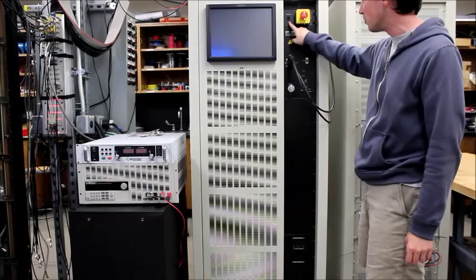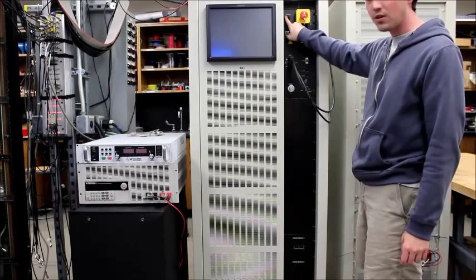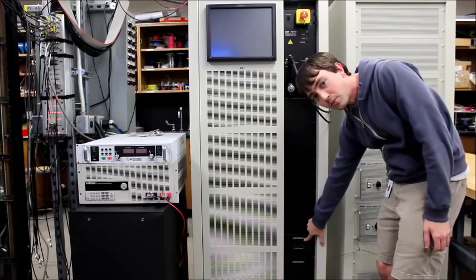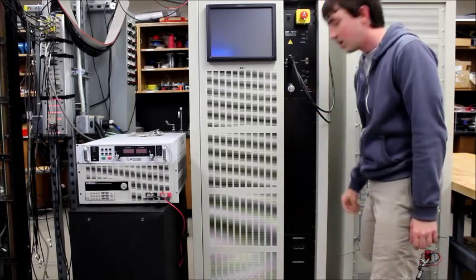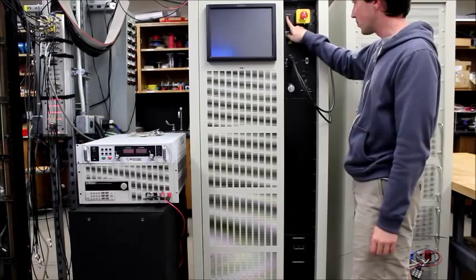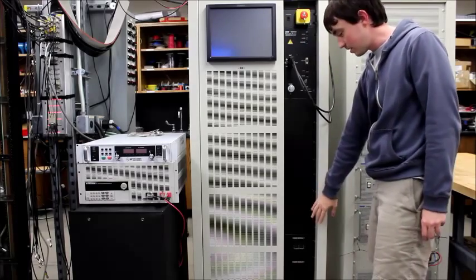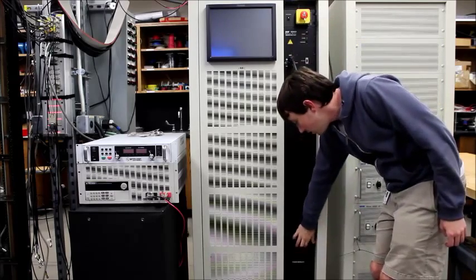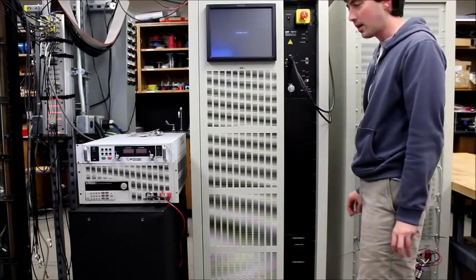To turn it on, there are two switches: one that says on standby, and the other one is the power module one breaker in the bottom. So if you look in the manual, it says to turn this switch on, and then within like 10 seconds to turn the breaker on. So I'm going to push that on and pull the breaker on all the way to the top.